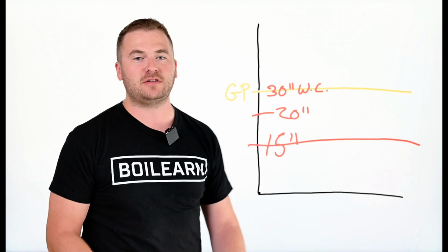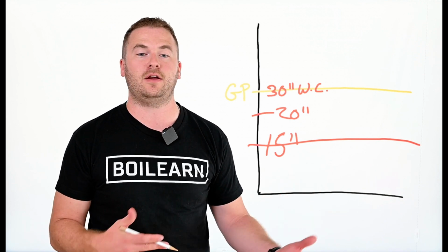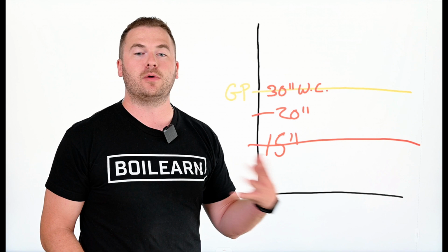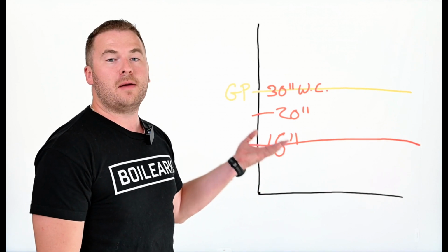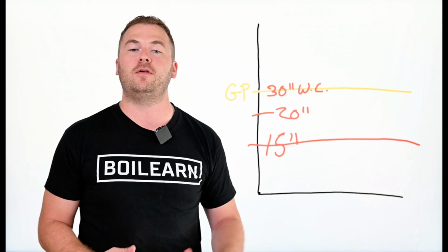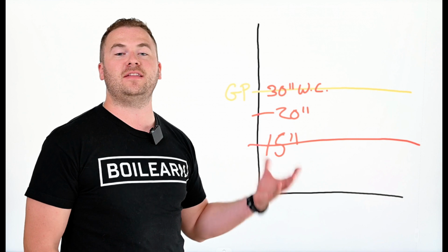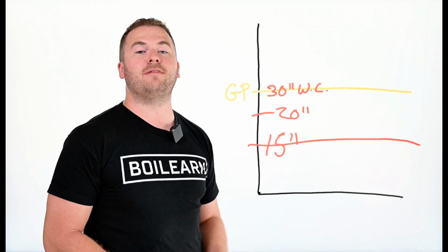But a lot of gas pressure switches are set from 3 to 21 or 3 to 60 or have different ranges. And we're going to avoid any set point below the 15 inches of water column, because we always have to be mindful that we are never going to set our low gas pressure switch less than 50% of the rated main manifold pressure. And that is the 3 criteria for setting the set point on a low gas pressure switch.